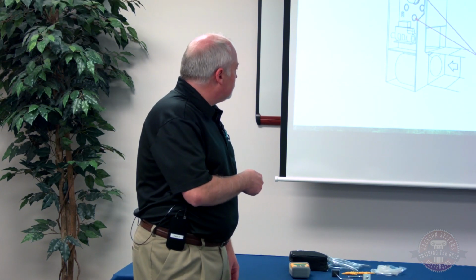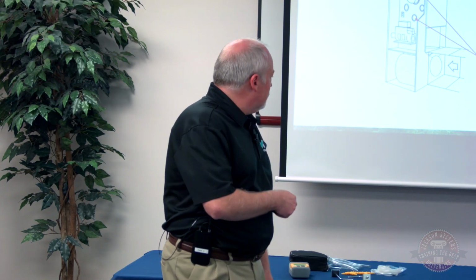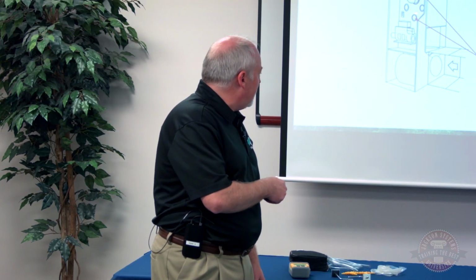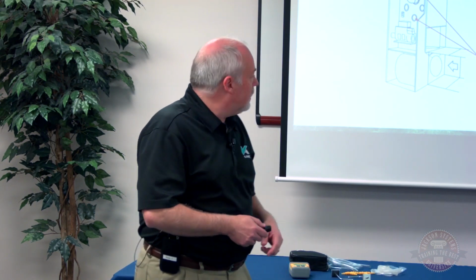One is in the flue, and that's what we're going to do when we set our barometric damper so that we've got the proper draft in the flue. And then we also have to check what they call overfire. So typically on oil-fired equipment, there is some type of inspection door on that. Sometimes there's a threaded plug that you can remove to check pressure. Sometimes we have to drill a hole if somebody hasn't checked it before, but we want to check that overfire.